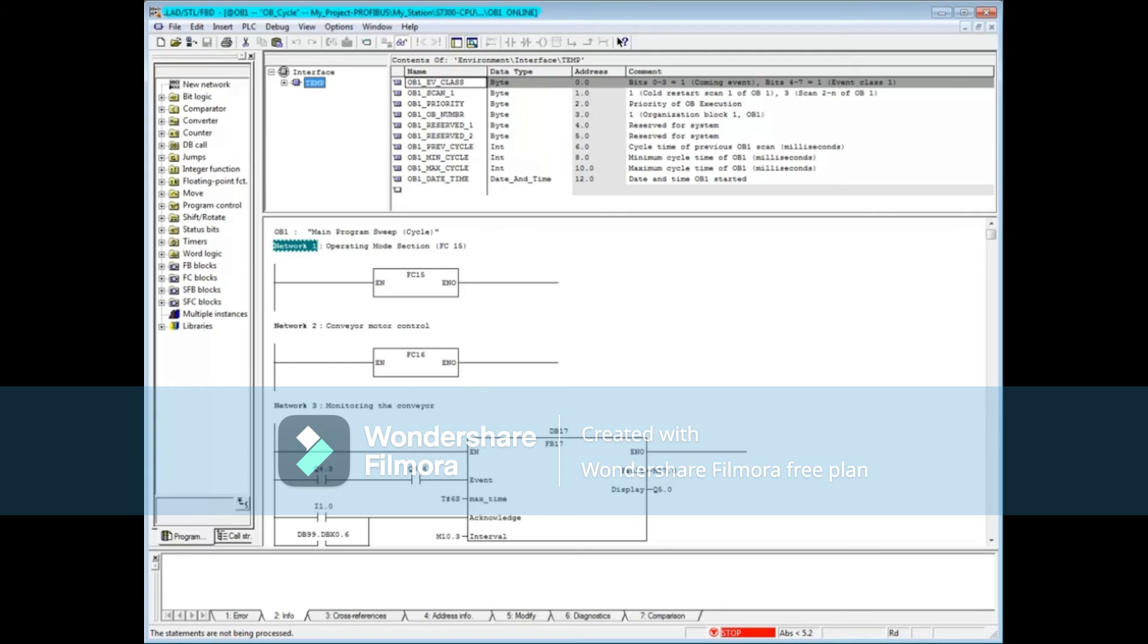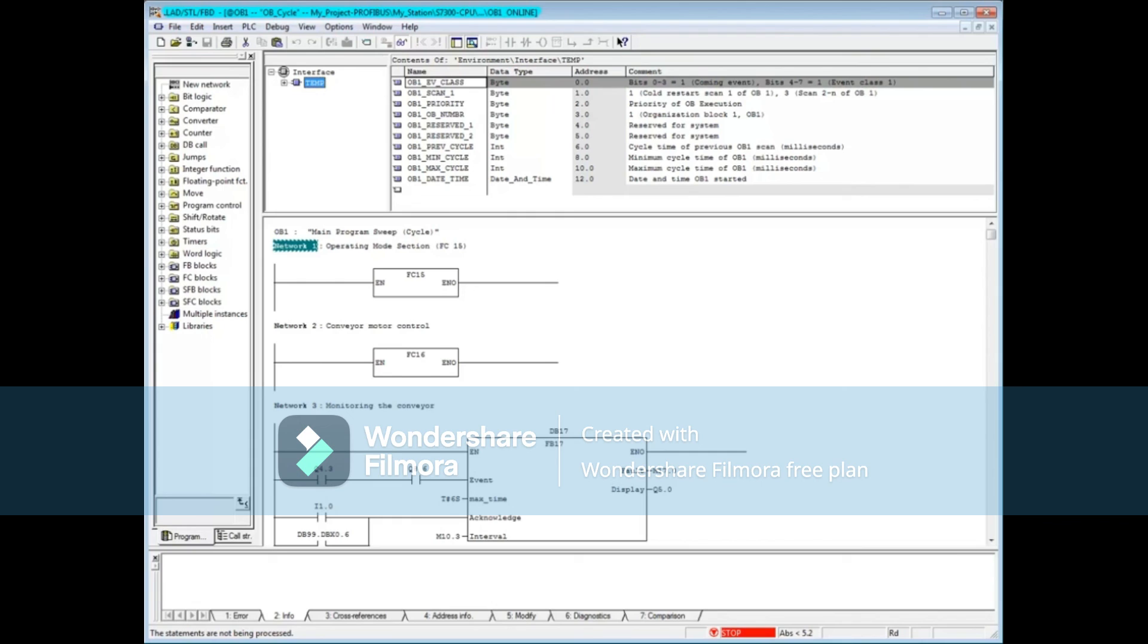In conclusion, if you have an error that involves block not downloaded or an address that's outside the range, the diagnostic buffer is sufficient for troubleshooting. If, however, you need to know what values are in the accumulators, address registers, and the status word, then the stacks tool would be very helpful. Remember that you have to be in stop mode to access the stacks tool. And that concludes this video.